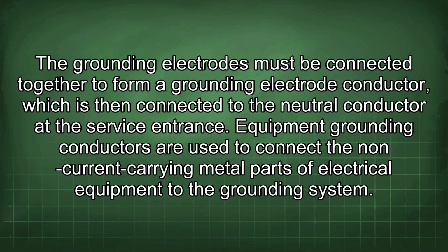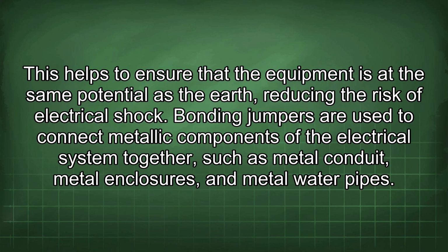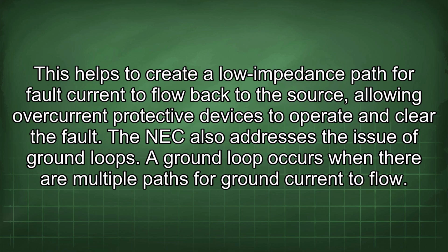Equipment grounding conductors are used to connect the non-current carrying metal parts of electrical equipment to the grounding system. This helps to ensure that the equipment is at the same potential as the earth, reducing the risk of electrical shock. Bonding jumpers are used to connect metallic components of the electrical system together, such as metal conduit, metal enclosures, and metal water pipes. This helps to create a lower impedance path for fault current to flow back to the source, allowing overcurrent protective devices to operate and clear the fault.